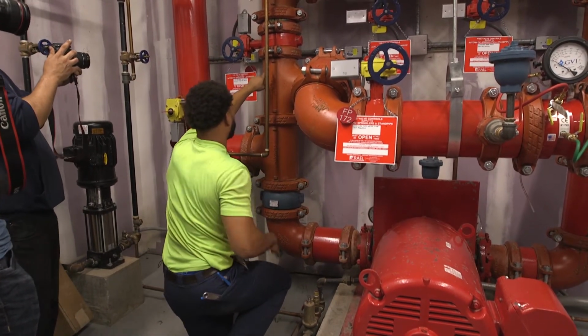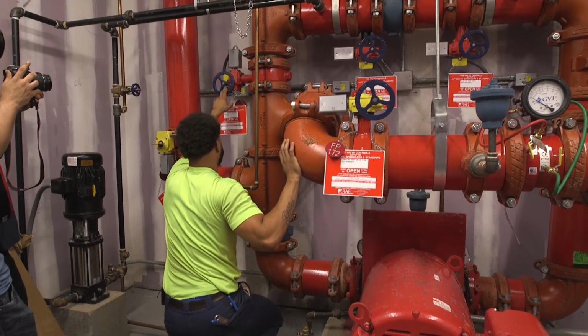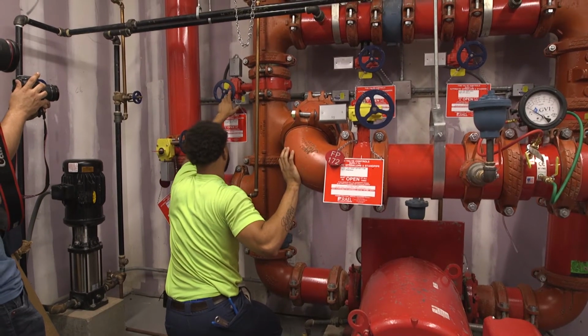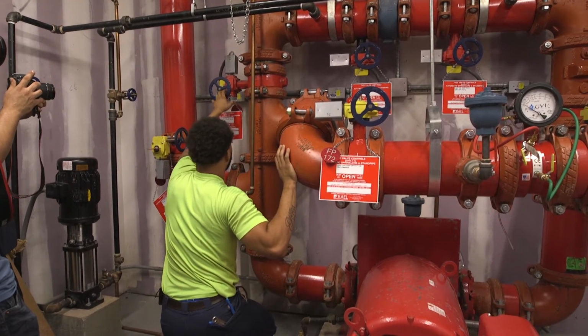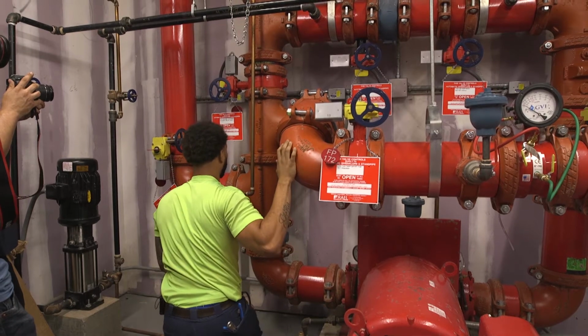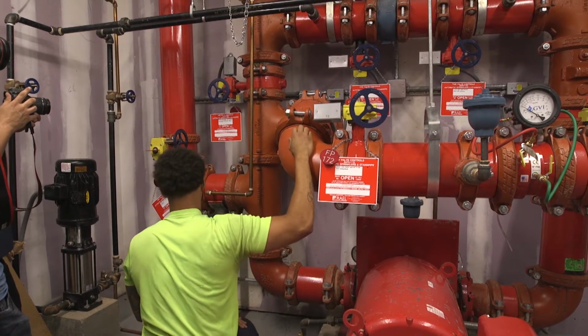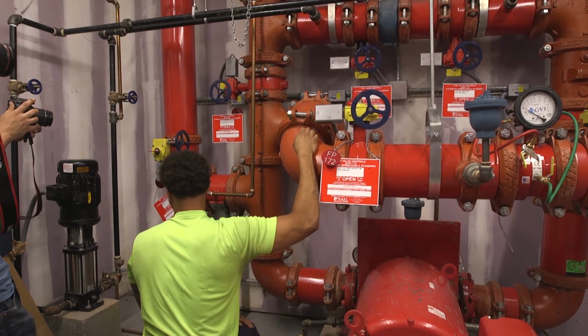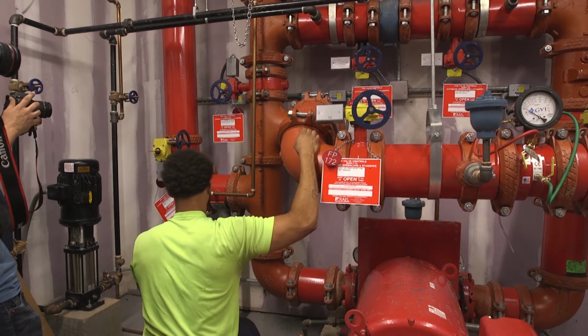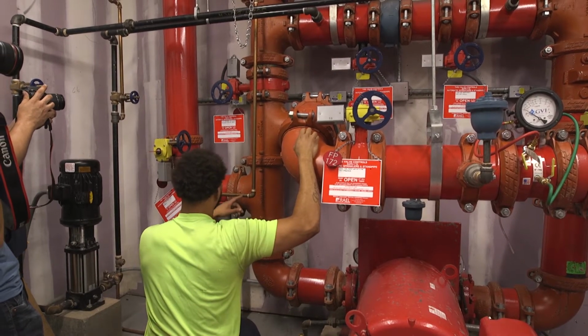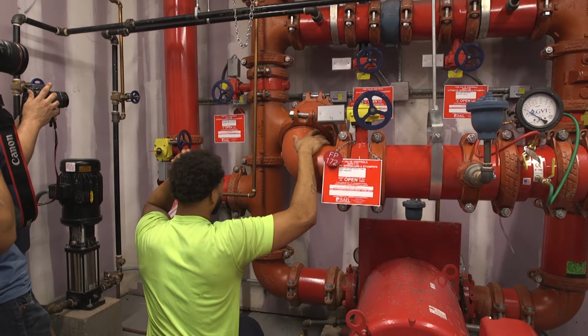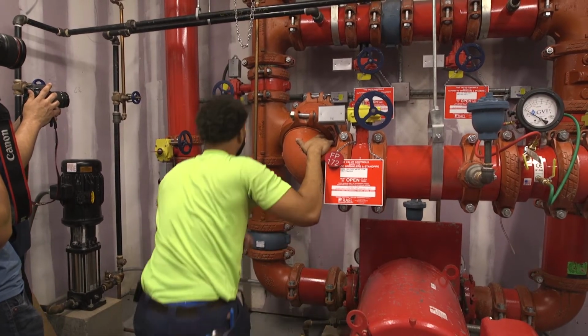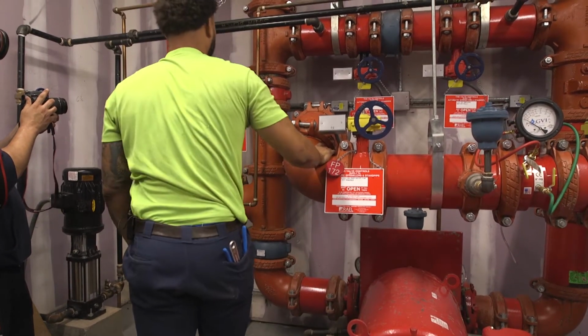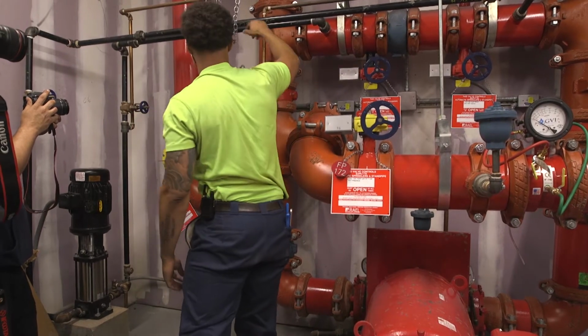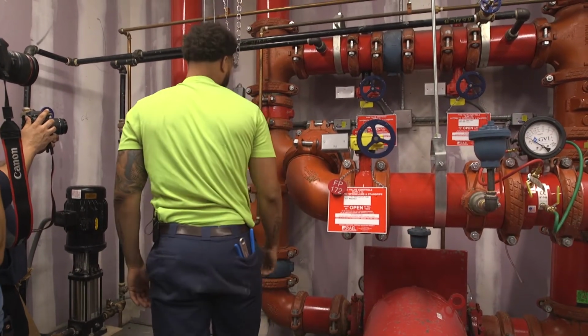If we keep looking up here, we have our discharge side isolation valve, which is a butterfly valve. Closing this valve is going to deadhead your fire pump, and say if you guys did have a fire, you would not be able to pressurize your system to put that fire out just because you have this valve closed. So the only pressure you'll be getting is your street pressure that's coming in from the street service.